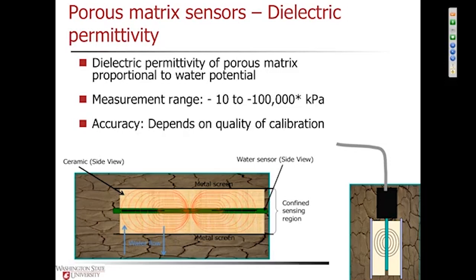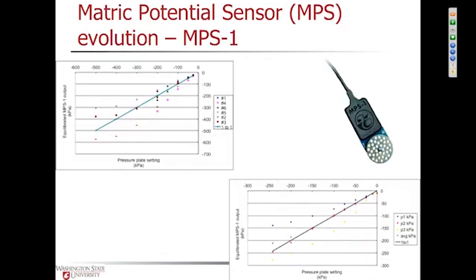So we want to tell you a little bit about what we've been doing with these sensors and what that means for your research. Before we get into that, with these sensors, the premise is the same as the others. You put a ceramic in the soil, and it equilibrates with the water potential of the soil, and then you measure the dielectric permittivity, which is an electrical property of a material, and that's proportional to the water content and therefore the water potential. The measurement range on these sensors is about -10 to -100,000 kilopascals, and I put a little star there by -100,000 because we get sensitivity to negative 100,000, but it's not going to be particularly accurate at negative 100,000 kilopascals. And again, with any of these indirect measurements, with any of these porous matrix sensors, the accuracy really depends on the quality of calibration, and that's what I want to talk about a little bit.